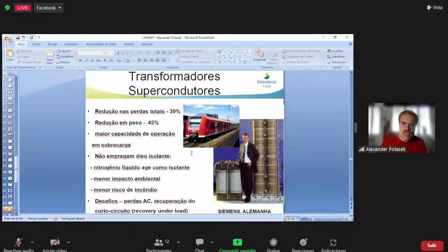Transformers, superconducting transformers, are another interesting thing because you can see here a comparison between a conventional transformer and the smaller one, a superconducting transformer. Again, it's quite interesting, for example, for transportation, because you save space and it's lighter, and it has a lot of advantages. However, nowadays the progress in this area is not that big because there are a lot of problems that are not yet resolved, such as the AC losses, and you have to recover after a short circuit under load. You cannot disconnect it after the short circuit. And you have a temperature rise and have to cool down under load.